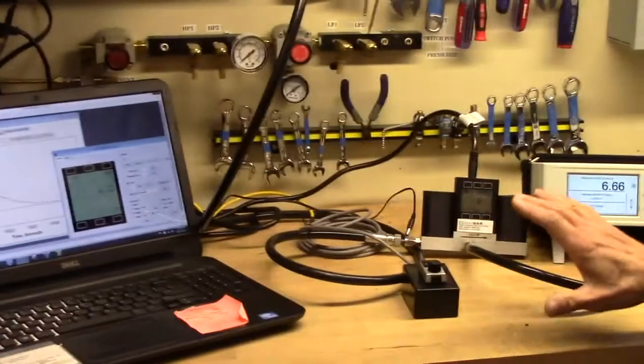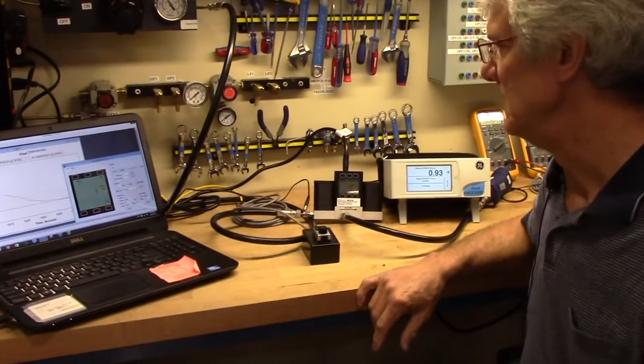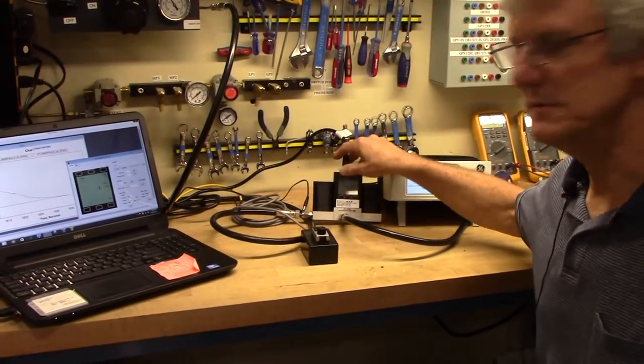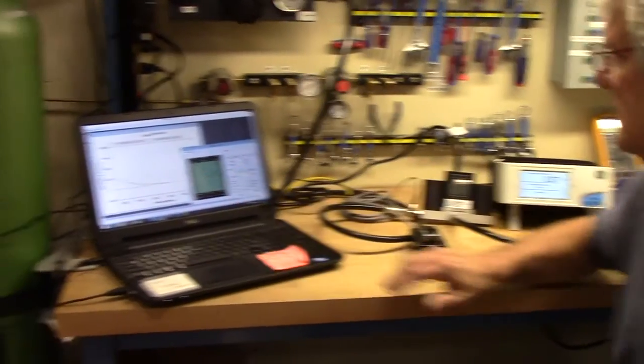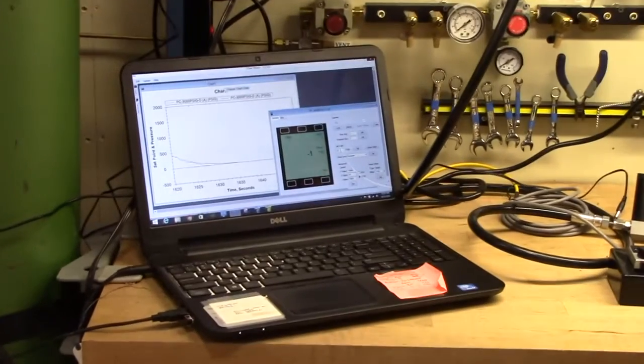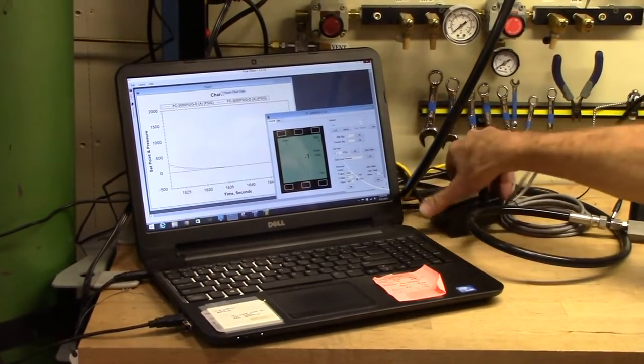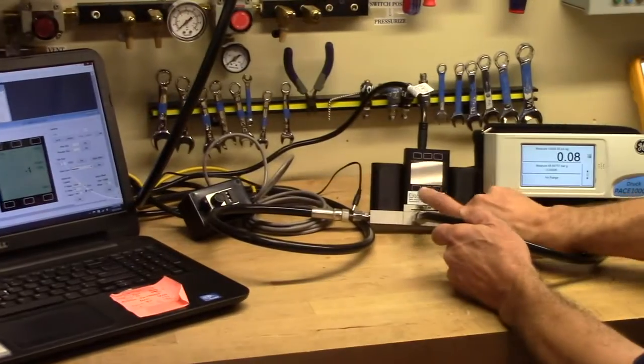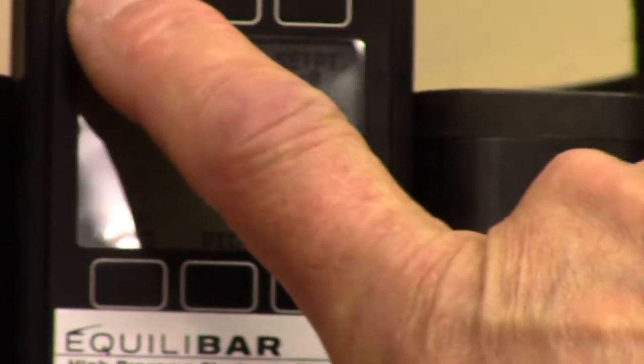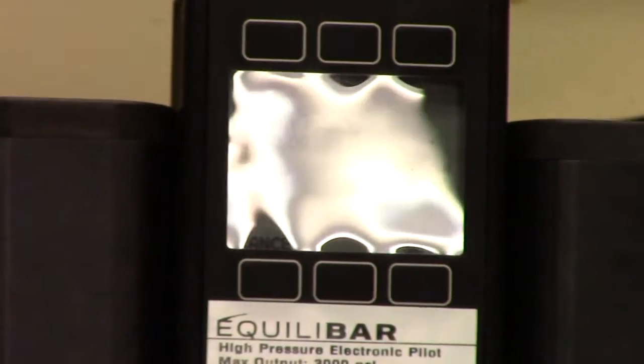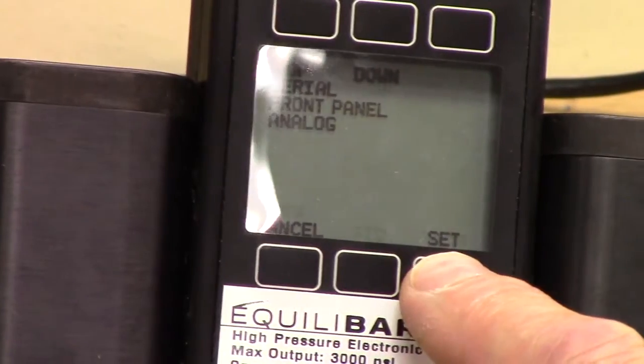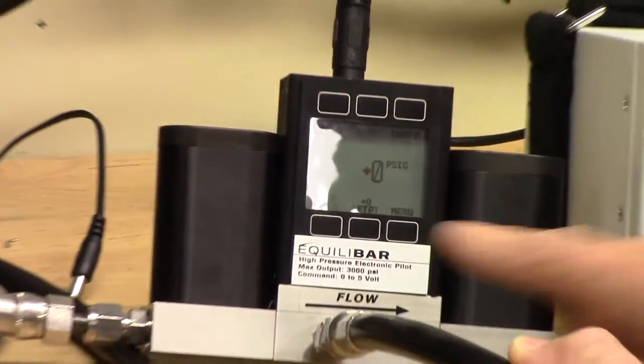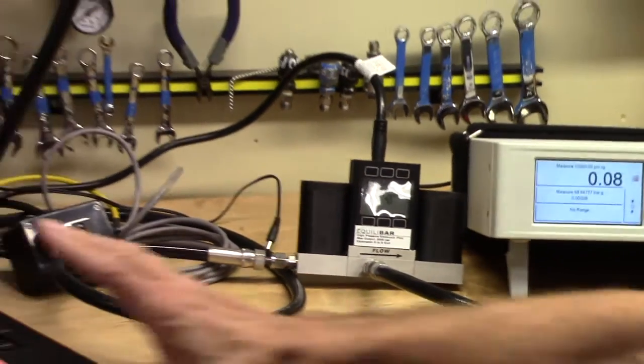Now a third method for controlling the EPR 3000 is through the RS232 port which is also on the mini DIN connector up here. We are using the FlowVision software. All I need to do is go and change the set point source. Go to menu, control setup, set point source and we're going to go to serial which is the top selection and we'll set. Now we're controlling the unit with the software.